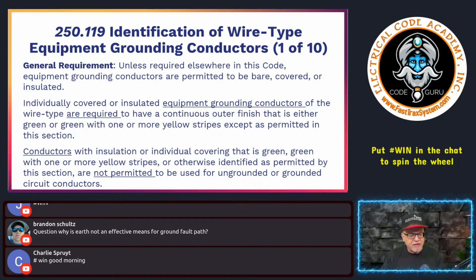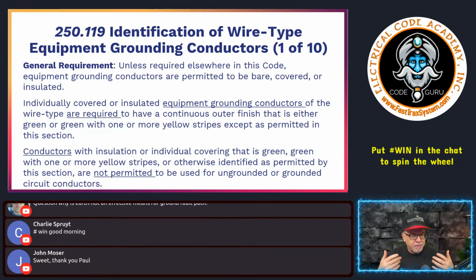But it's also there to help with bonding, which is tying all metal parts together. That's why we're required in the code to have an equipment grounding conductor. That's why we're required to bond the metal boxes. That's why we're required to bond the raceways. And we can utilize an equipment grounding conductor or equipment bonding jumper, which ultimately comes together to the equipment grounding conductor in those systems to achieve this. So that's what that conductor is there for.